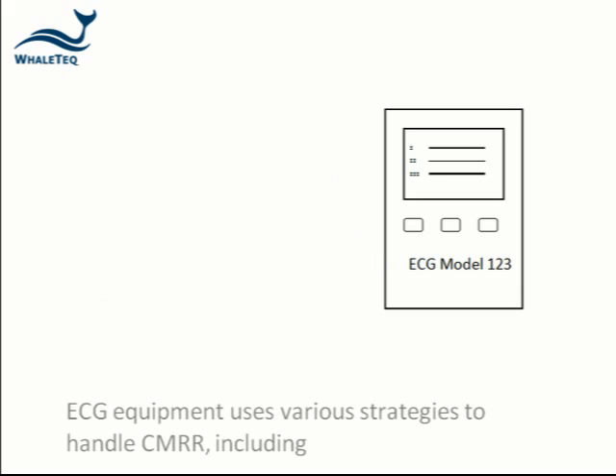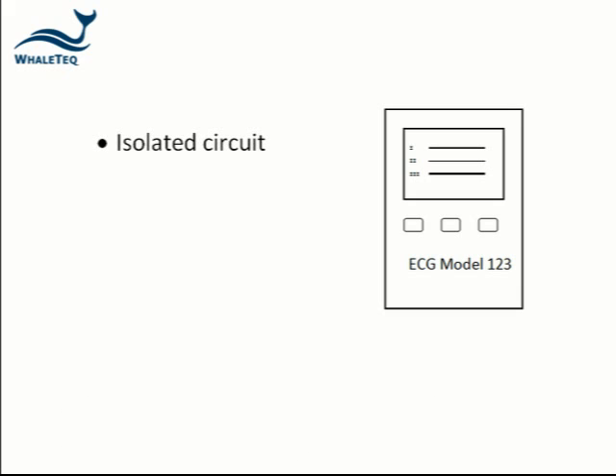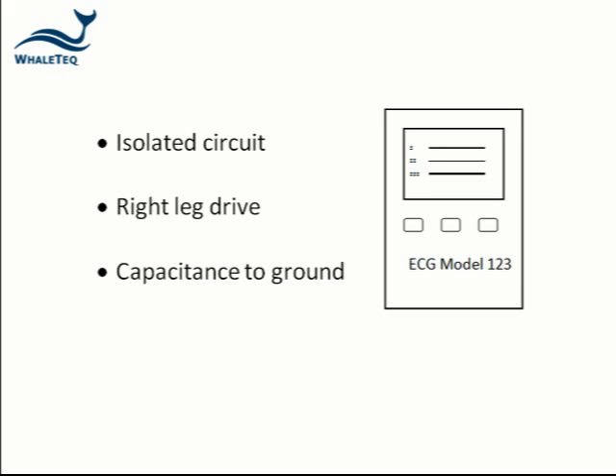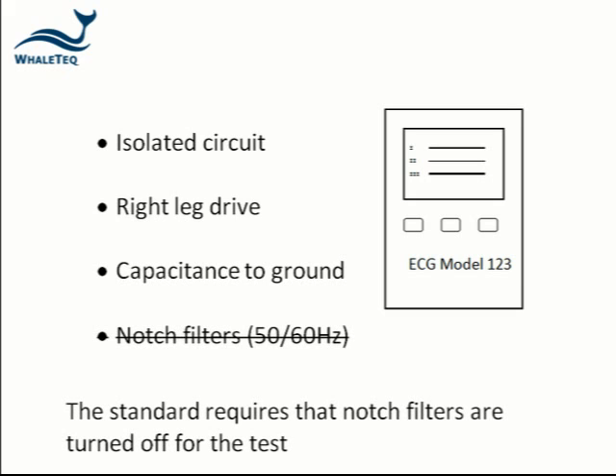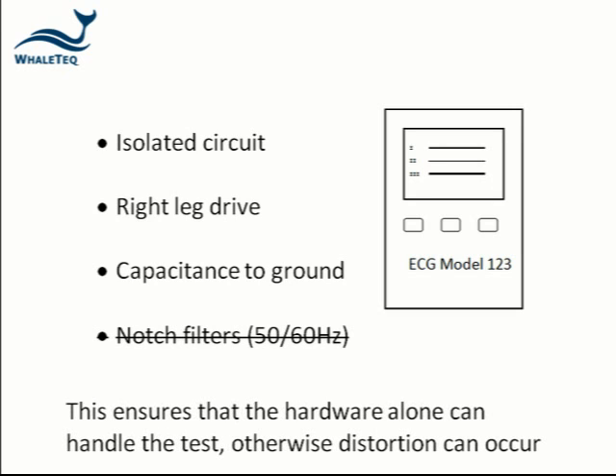ECG equipment uses a variety of strategies to handle CMRR, including an isolated circuit, right leg drive, capacitance to ground, and filtering. However, the standard requires that special mains filters are turned off for the test. This is to make sure that the hardware alone can really handle the test, otherwise the ECG trace can get distorted.